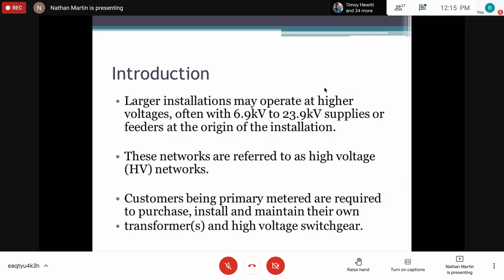We talk about the larger installations, which are the heavy-duty installations. They operate at voltages between 6.9 kilovolts and 23.9 kilovolts, or 24 kilovolts, and it varies for different regions depending on the generators. These networks are referred to as high voltage or medium voltage networks in some regions. Customers being primary metered are required to purchase, install, and maintain their own transformers. So heavy-duty industry customers would definitely need to purchase, install, and maintain the transformers they use at their service entrance to supply their high-voltage switchgear.